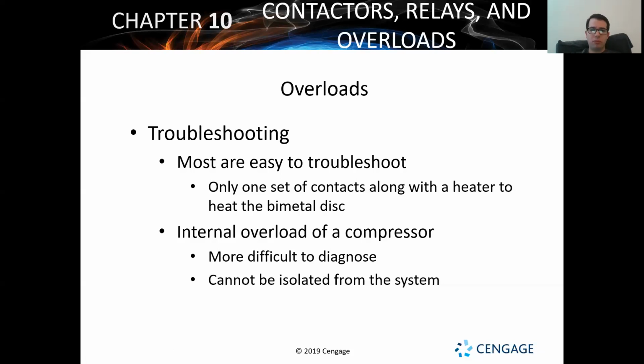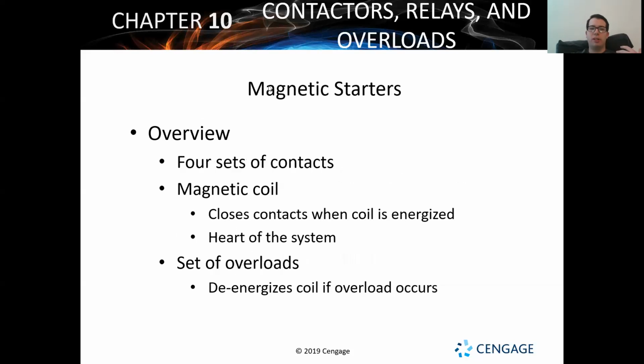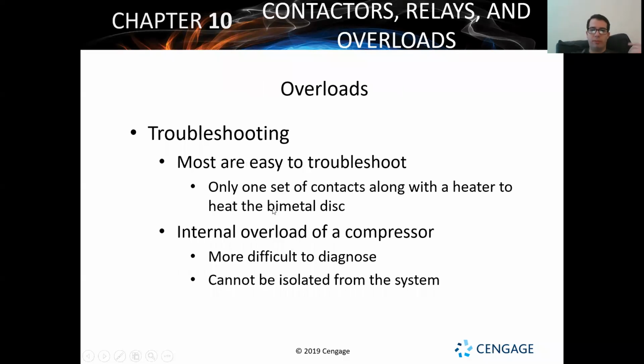So we got a couple of different ones. The only difficult one, like it's saying right here, is the internal overload of a compressor. The tough one with that is typically those overloads will be set where it's going to be about 5 minutes. It could be more, could be less, than 5 minutes. But typically your internal overload of a compressor is going to be either time or temperature sensitive, more commonly.